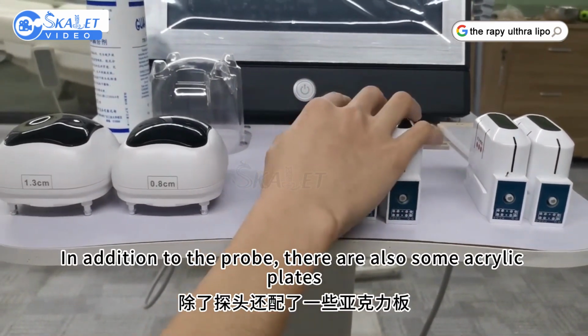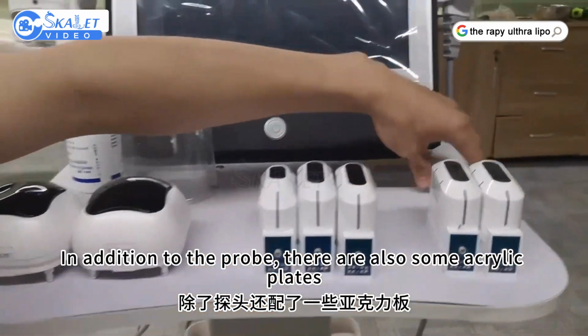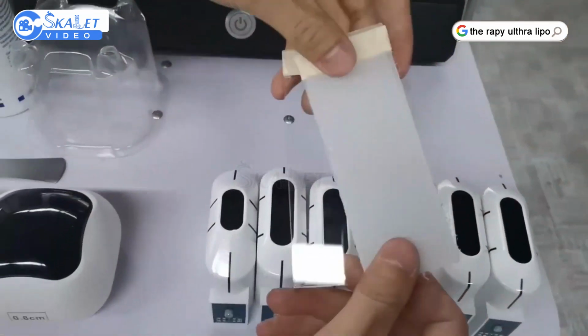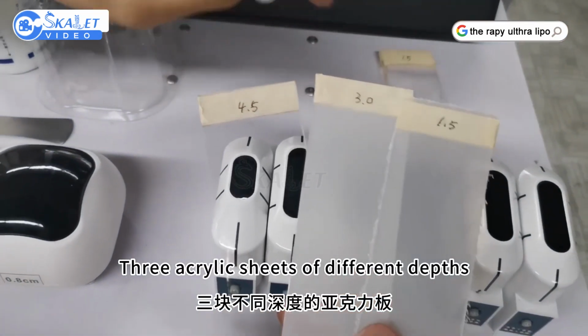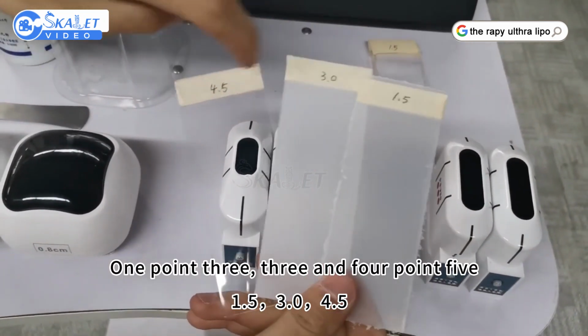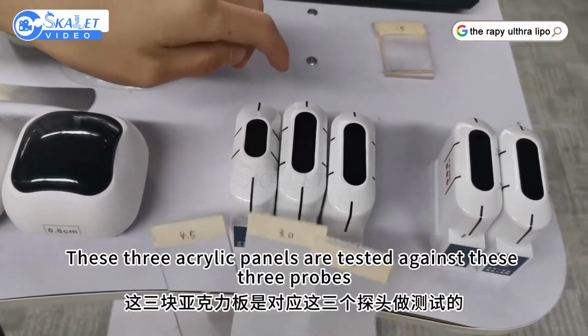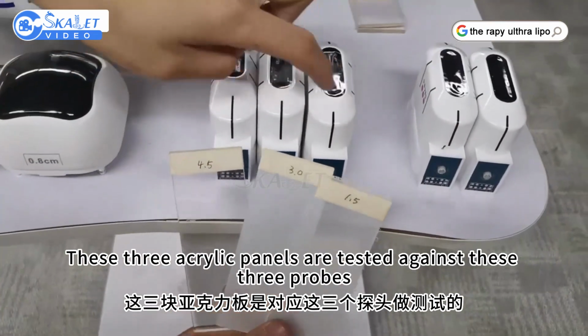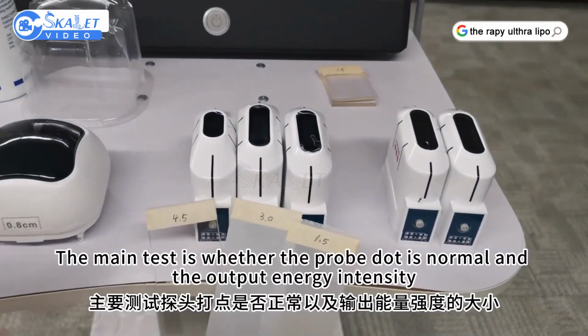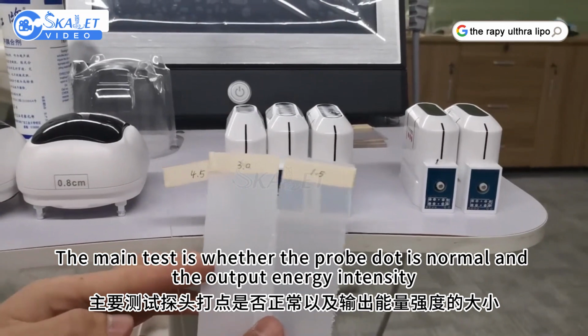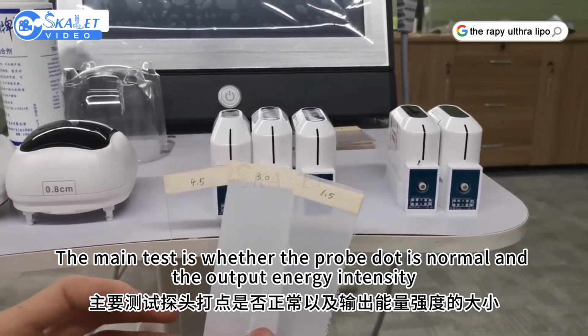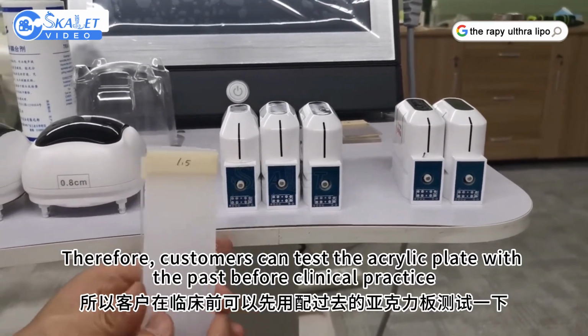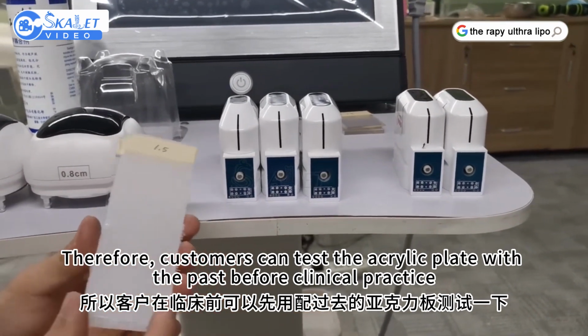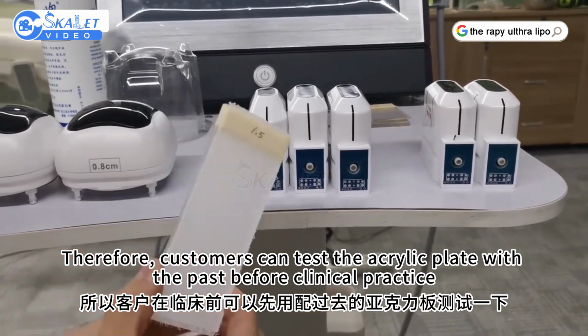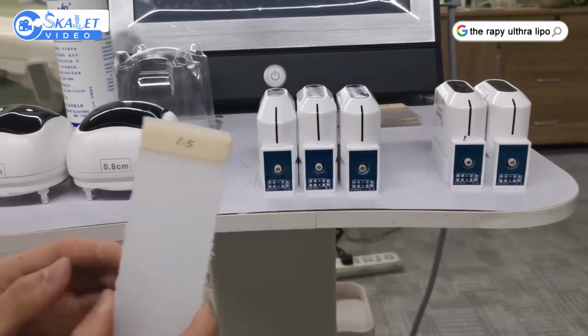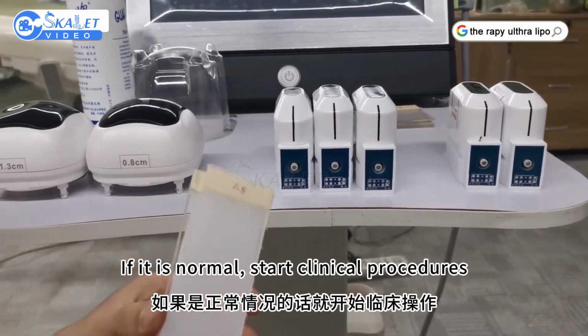In addition to the probe, there are also some acrylic plates. 3 acrylic sheets of different depths, 1.5, 3 and 4.5. These 3 acrylic panels are tested against these 3 probes. The main test is whether the probe dot is normal and the output energy intensity. Therefore, customers can test on the acrylic plate first before clinical practice. If it is normal, start clinical procedures.